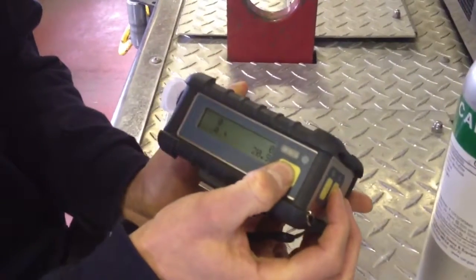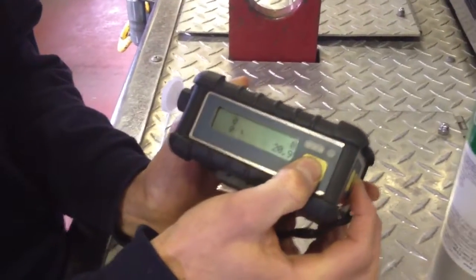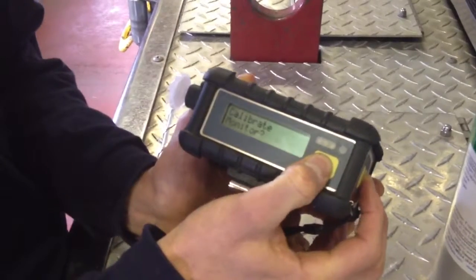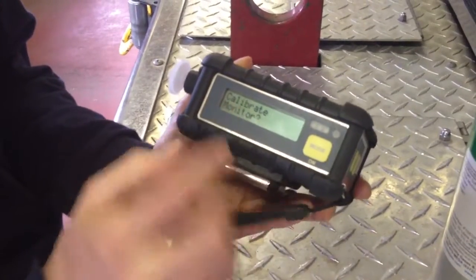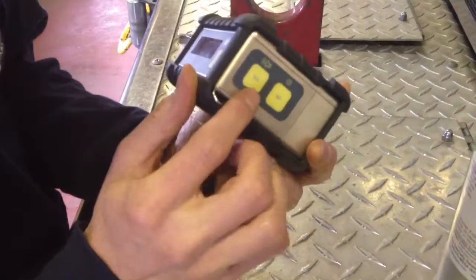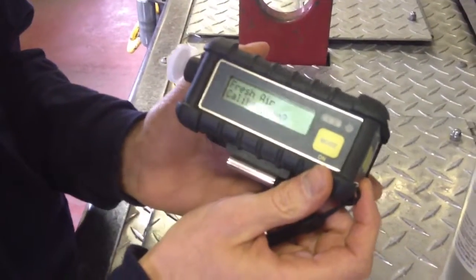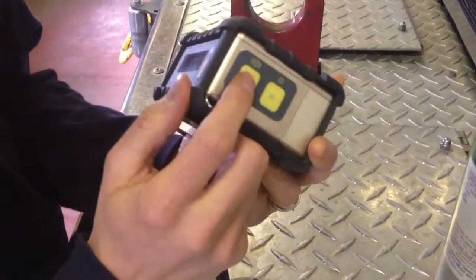First, we're going to hit the no button and the mode button at the same time and hold both of them down. The monitor is going to go into data log paused. You can let go, and it's going to ask if we want to calibrate the monitor, and we'll say yes. Then it asks if we want to do a fresh air calibration, and we'll say yes.